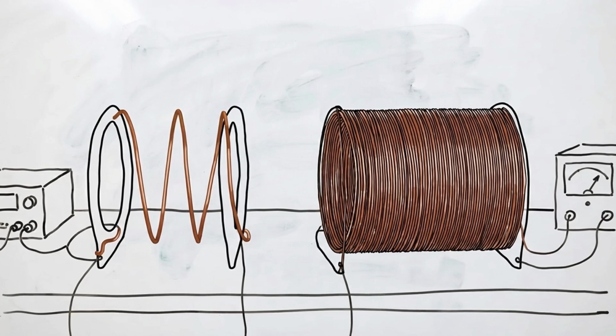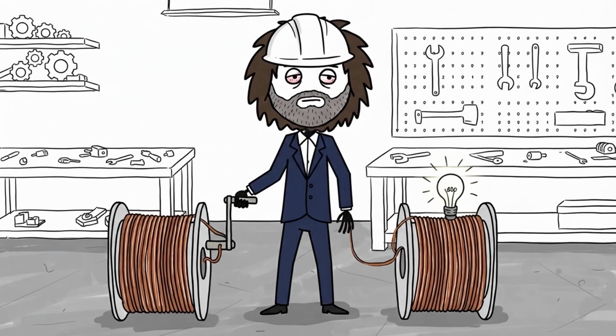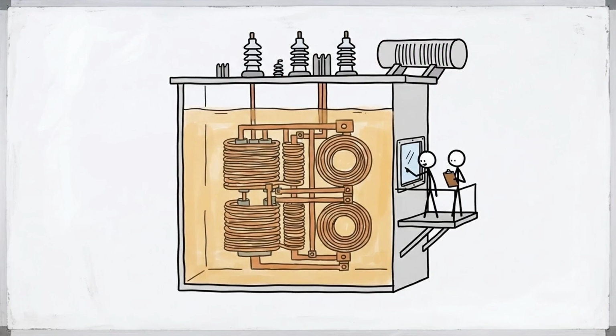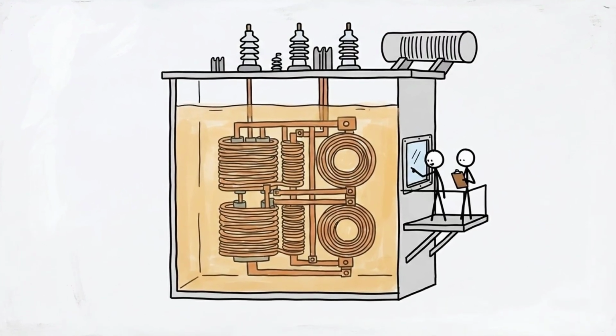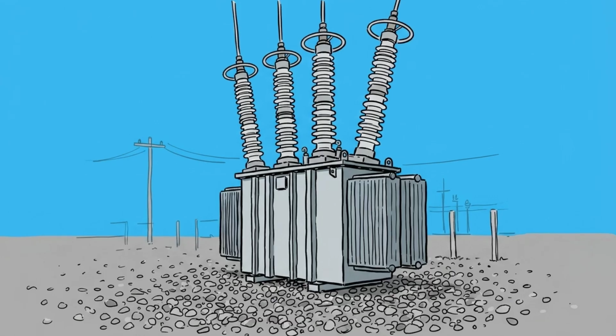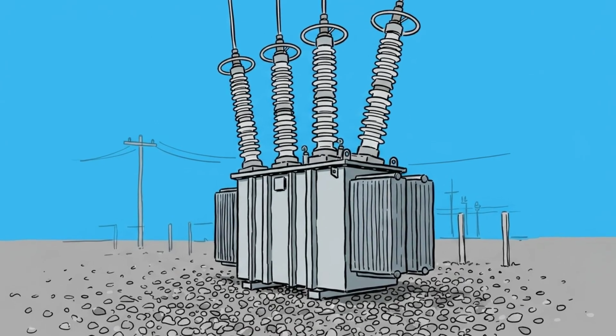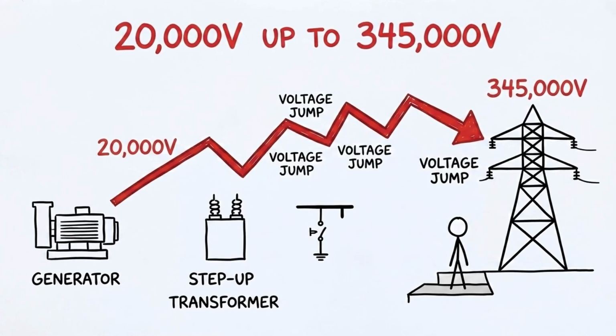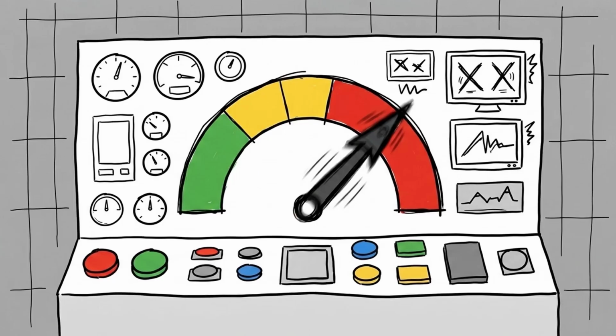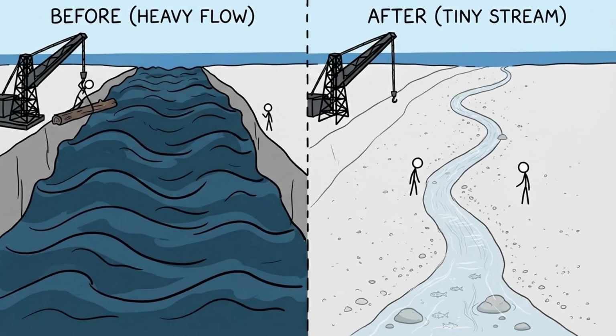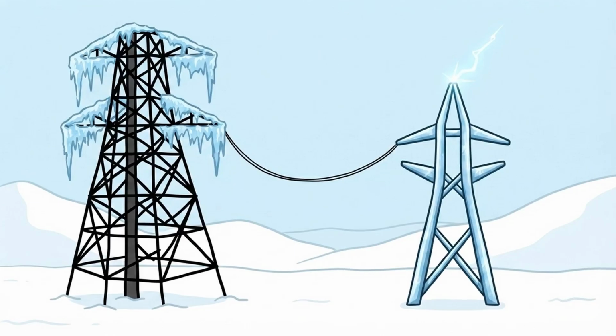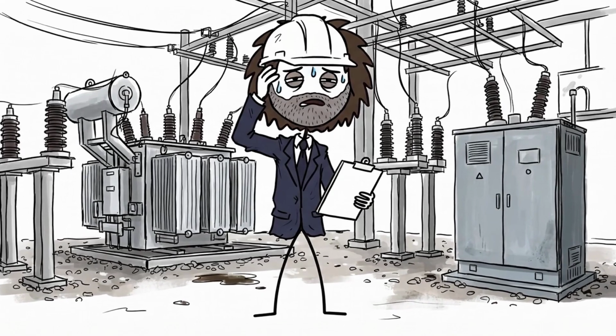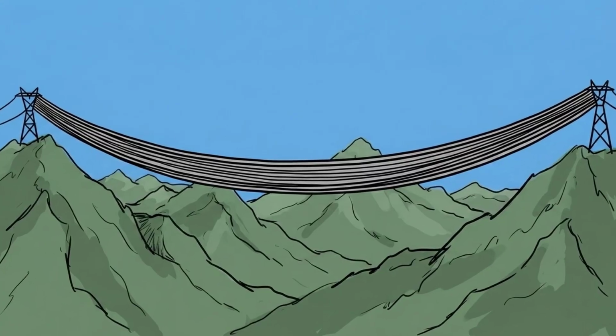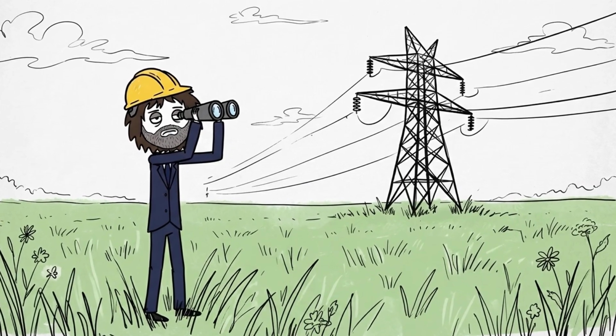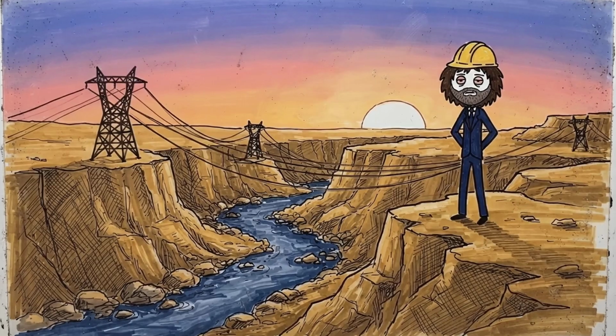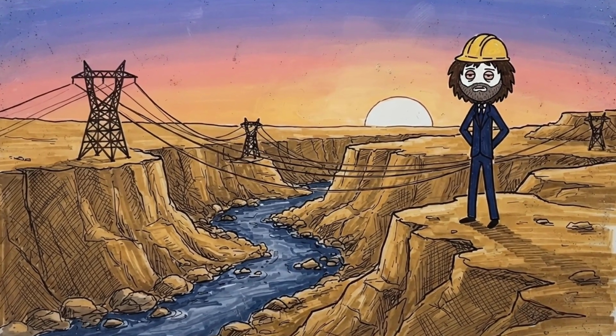To solve this, the electricity immediately leaves the generator and enters the power plant's high-voltage step-up substation, home to massive oil-cooled transformers the size of a two-story house. Inside these steel tanks, primary and secondary copper windings wrapped around a laminated iron core use magnetic flux to do something incredible. They drastically jack up the electrical pressure, boosting the voltage from 20,000 volts all the way up to staggering levels like 230,000, 345,000, or even 765,000 volts. By boosting the voltage that high, the required current drops to a tiny fraction of its original flow, allowing massive amounts of energy to glide across hundreds of miles of open countryside with minimal heat loss.